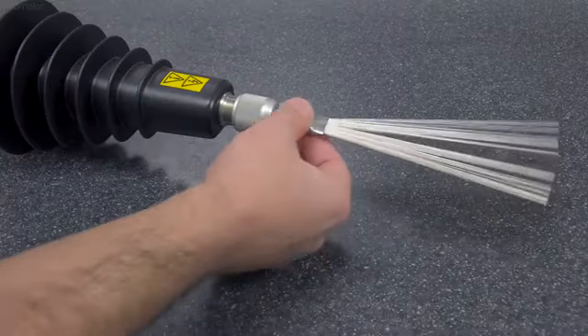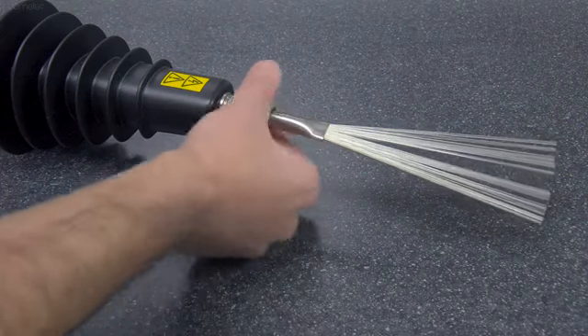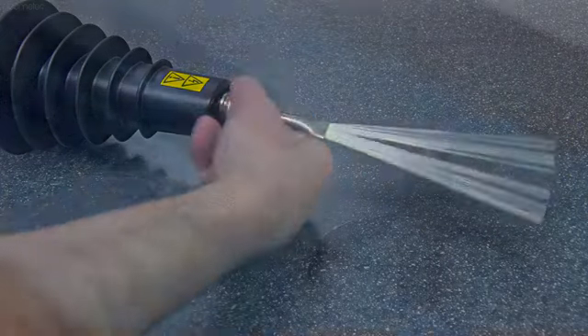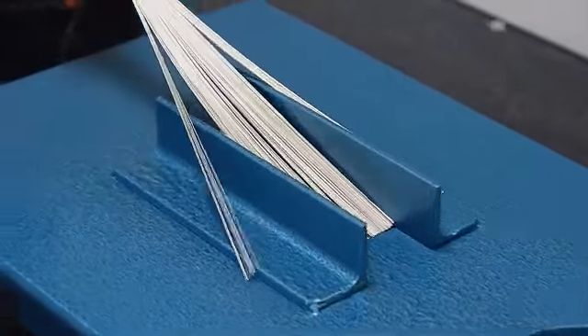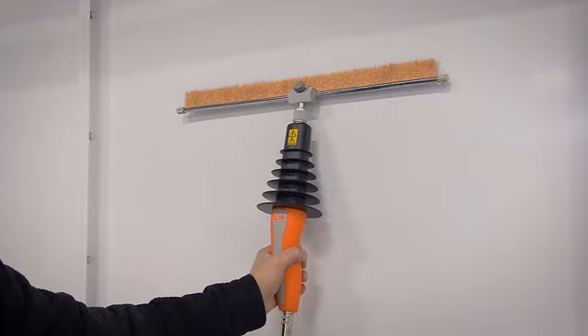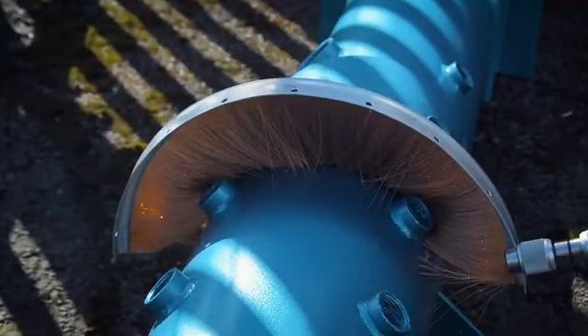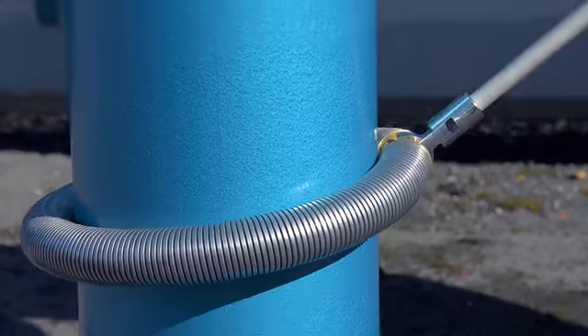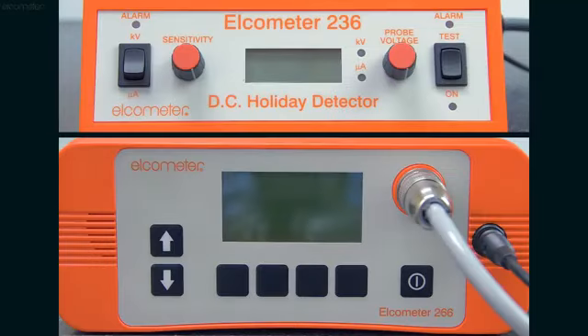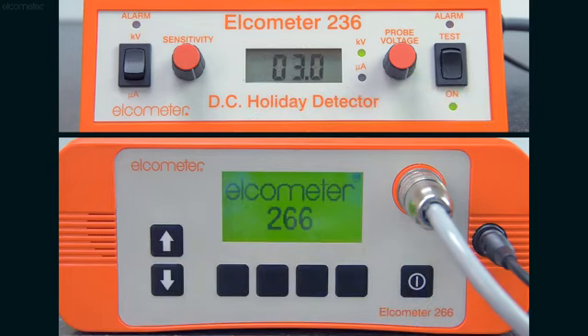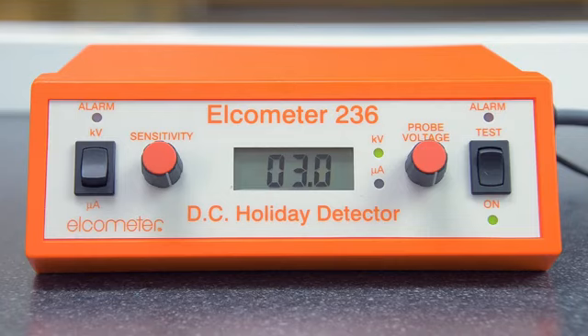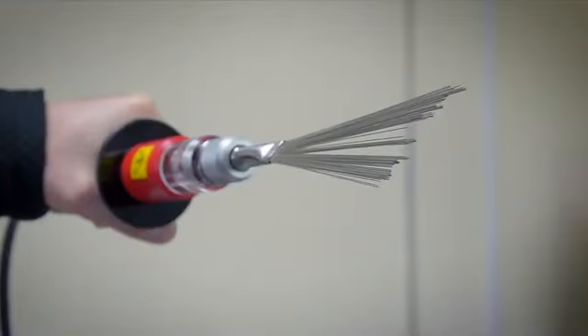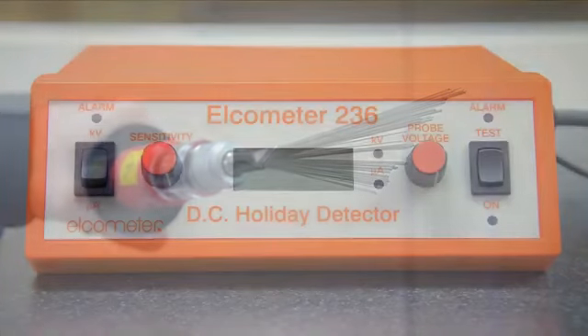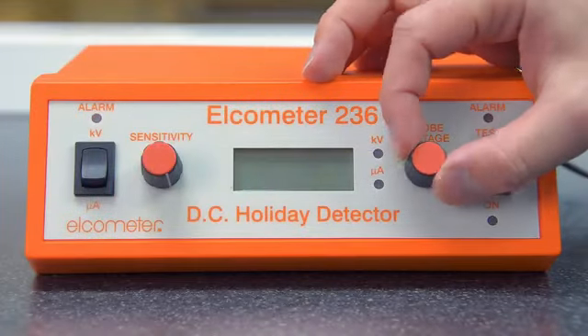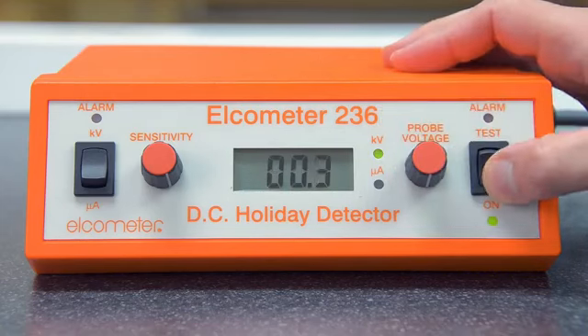Next, fit the probe you'll be testing with to the probe handle. A band brush is supplied as standard with both gauges as it's ideal for most applications, but there are a wide range of probes for different applications and coating types. There's a separate video on choosing the right probe for your application later in the series. With your chosen probe fitted, switch on the holiday detector. Please note, the moment the Elcometer 236 is switched on, the voltage displayed on the LCD screen will be delivered to the probe tip. As a result, we recommend the voltage is set to 0 before switching on. Simply turn the probe voltage control fully anti-clockwise to do this.